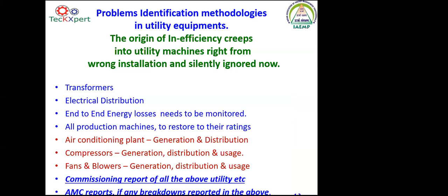Normally we find, in any of the machines or utility equipment, from transformers to all the electrical distribution equipment, switchgear, motors, and pumps, the origin of inefficiency starts in the utility machines right from the date of installation. There are more than a hundred participants here. In all your industries, you go and see your screw compressor. Every screw compressor will be working like a box only. It needs a duct-type hood on top of the screw compressor so that the hot air can be exhausted easily out of the compressor house.